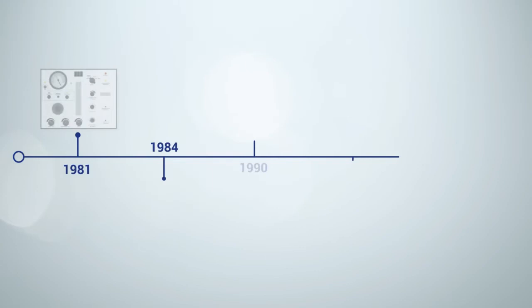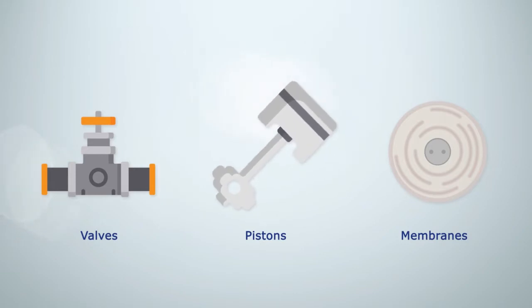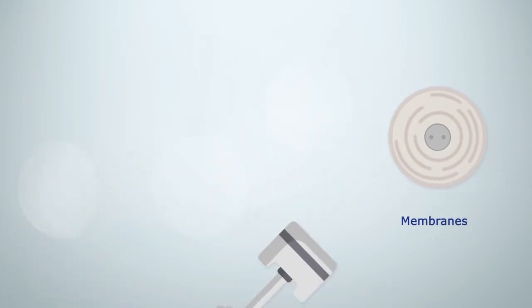Over the years neonatal ventilator manufacturers have used a variety of ways of controlling the ventilation a baby receives. These include valves, membranes and pistons in a multitude of configurations but each of these systems can be problematic.